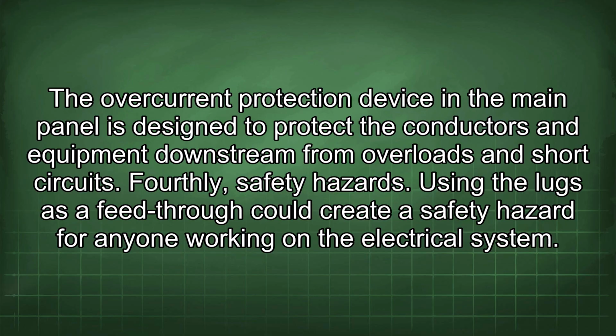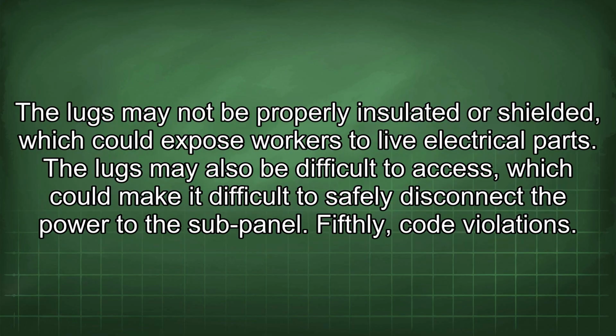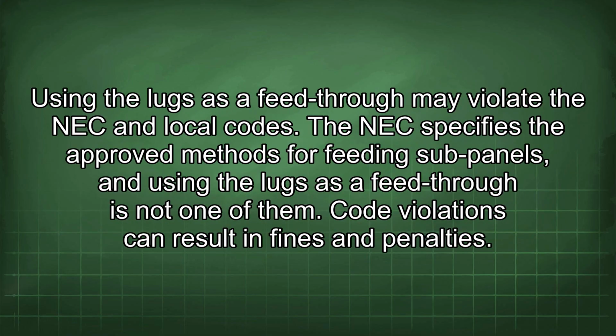The overcurrent protection device in the main panel is designed to protect the conductors and the equipment downstream from overloads and short circuits. Fourthly, safety hazards. Using the lugs as a feed-through could create a safety hazard for anyone working on the electrical system. The lugs may not be properly insulated or shielded, which could expose workers to live electrical parts. The lugs may also be difficult to access, which could make it difficult to safely disconnect the power to the sub-panel. Fifthly, code violations. Using the lugs as a feed-through may violate the NEC and local codes.